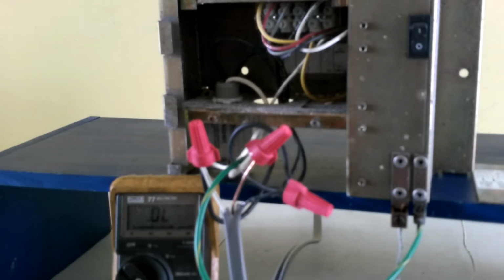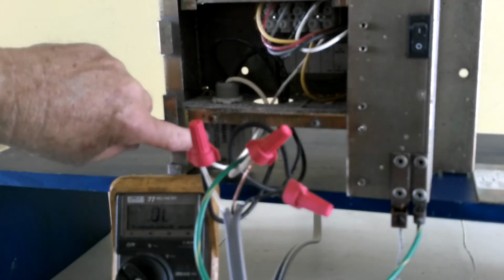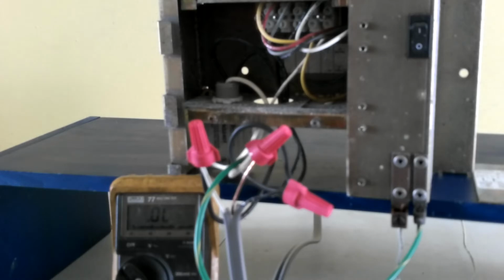Now, if they're in place, everything has been working, you come in and you find that the circuit breaker for that power supply has tripped, indicating that there is a short, which has caused it to disconnect. The first step is make sure the breaker is off, then go out and inspect each of your field satellites that are on that power supply. In particular, check the surge arrestor. Usually, you will find that the surge arrestor has done its job. It's protected your satellite, but it's also shorted itself out internally.